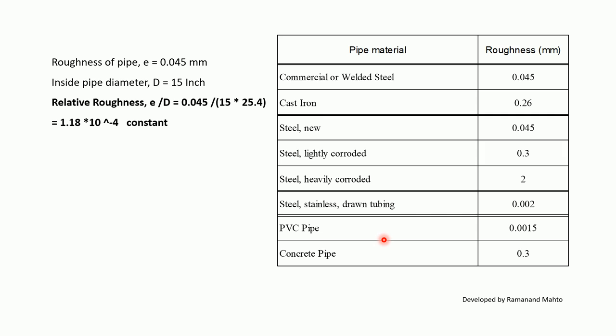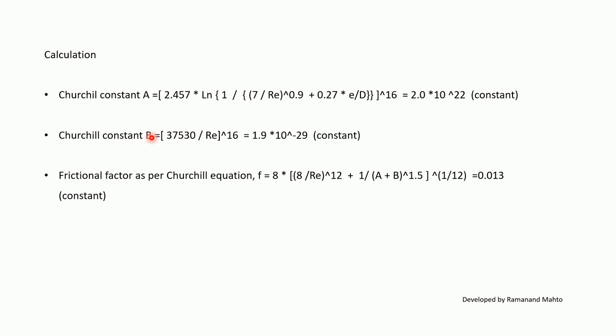From the chart, roughness of pipe e = 0.045 mm and inside pipe diameter = 15 inches. Relative roughness = 0.045 / (15 × 25.4) = 1.18 × 10⁻⁴. Churchill constant A = 2.0 × 10²². Churchill constant B = 1.9 × 10⁻²⁹. Friction factor from Churchill equation = 0.013.